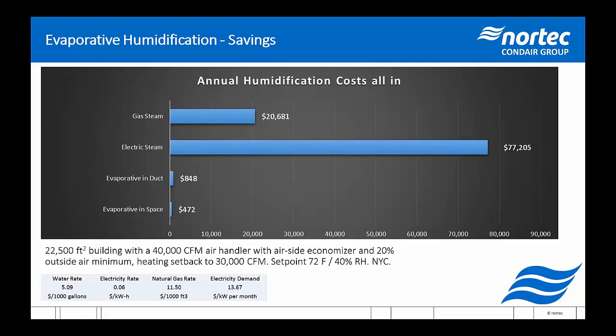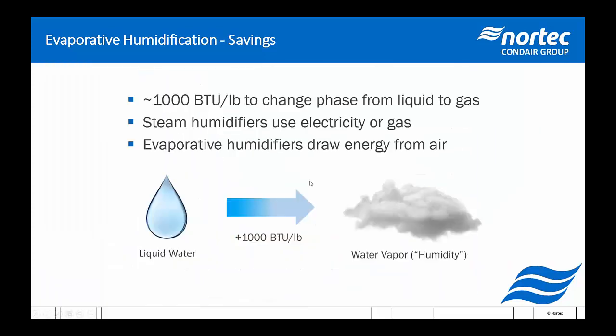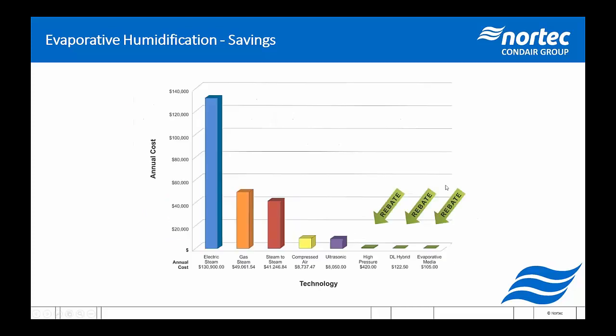So I have a question: could I repeat the relation between flow of water into space and BTU per hour? If we go back to here, when we're humidifying, we measure in pounds per hour typically. And so 1 pound per hour would be 1,000 BTUs per hour to put water into the space, no matter where it's coming from, plus or minus efficiencies. I hope that answers the question. Generally, I'm going to leave questions to the end, but if I notice that it's a quick answer, I'll answer it right away.